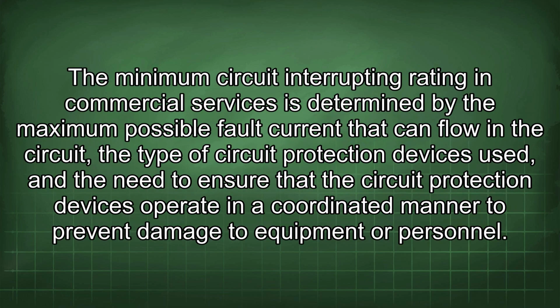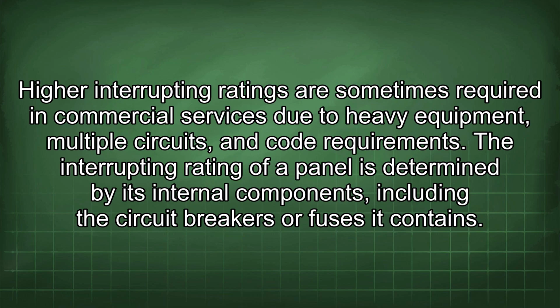The minimum circuit interrupting rating in commercial services is determined by the maximum possible fault current that can flow in the circuit, the type of circuit protection devices used, and the need to ensure that the circuit protection devices operate in a coordinated manner to prevent damage to equipment or personnel. Higher interrupting ratings are sometimes required in commercial services due to heavy equipment, multiple circuits, and code requirements.